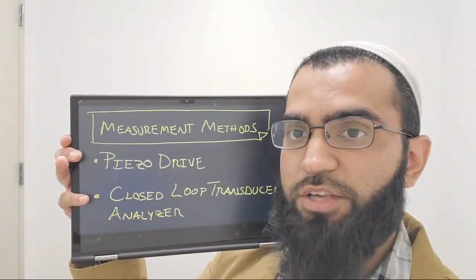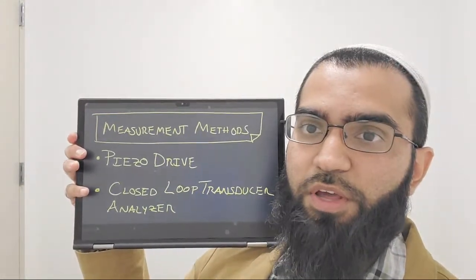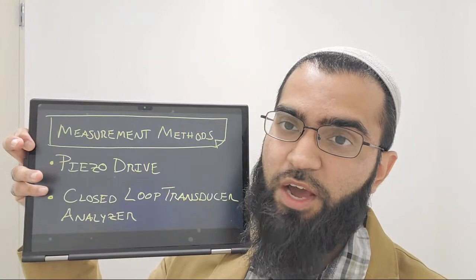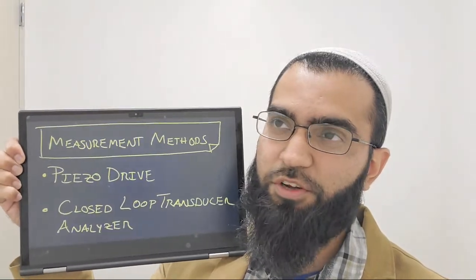All right, there's the last two, the notable mentions. So the one is Piezo Drive. Piezo Drive is a company that develops ultrasonic amplifiers for ultrasonic devices. They also have a box which has an amplifier built in. So you can do high voltage frequency sweeps. You can do constant current frequency sweeps. It also has the additional functionality of locking onto a certain phase. So that's also a very capable solution for that. Higher voltage, it's in the range of several thousand. It's not extremely expensive, much less. I believe it's going to be much less than your impedance analyzer for sure.